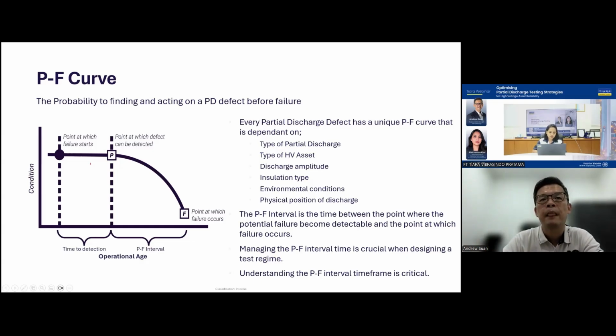Okay. Number 5, environmental conditions. In general, our electrical assets don't like high humidity. That's why in a modern switchgear substation, we install aircon, because we want to control the temperature and the humidity. These environmental conditions are very important, especially in Southeast Asia where the humidity is high. When humidity is high, you tend to have more surface discharge.